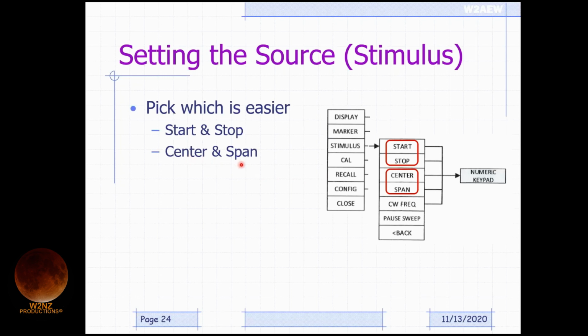Or sometimes, maybe if you're measuring a bandpass filter, it might be easier to set the center frequency and then the frequency span around that center frequency. So you can choose any combination of these to make a measurement, but it's usually setting the start and stop, or setting the center frequency and span. Anytime you select any of those, a numeric keypad pops up to allow you to enter it.